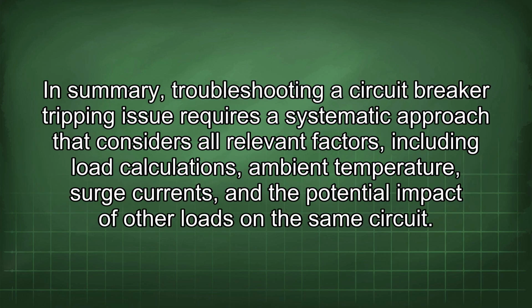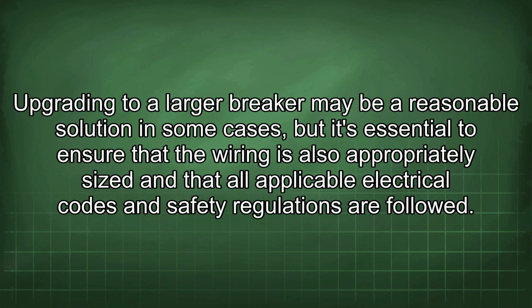In summary, troubleshooting a circuit breaker tripping issue requires a systematic approach that considers all relevant factors, including load calculations, ambient temperature, surge currents, and the potential impact of other loads on the same circuit. Upgrading to a larger breaker may be a reasonable solution in some cases, but it's essential to ensure that the wiring is also appropriately sized and that all applicable electrical codes and safety regulations are followed.